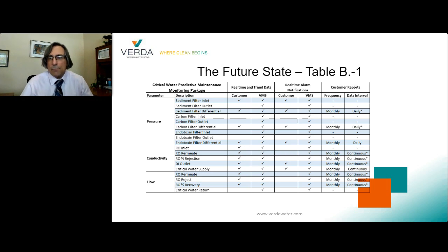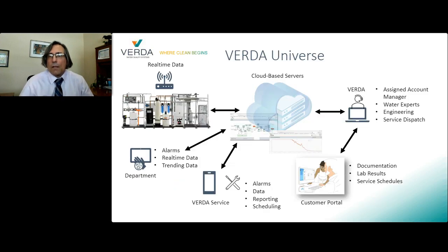In the table, we can see that we are monitoring the inlet and outlet pressure of the water coming into the ultrafilter. We sample the data every few seconds and it allows us to compute a pressure differential across the filter. If the value drops below the minimum for an intact filter, the system will trigger an alarm and send everyone a text or email. The customer can access real-time data and look at trends over a defined time period from screens in their work area.